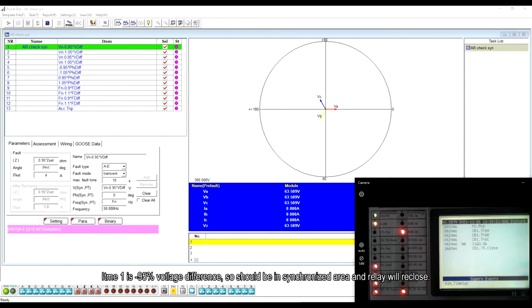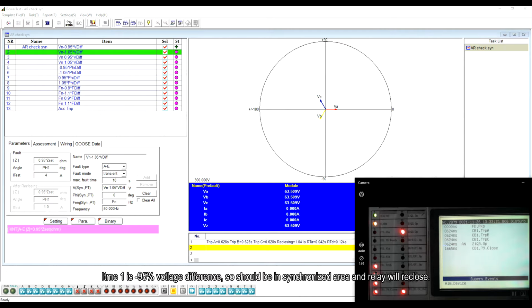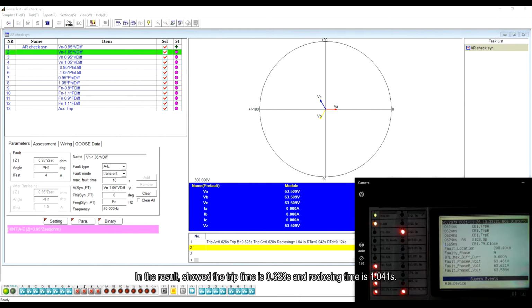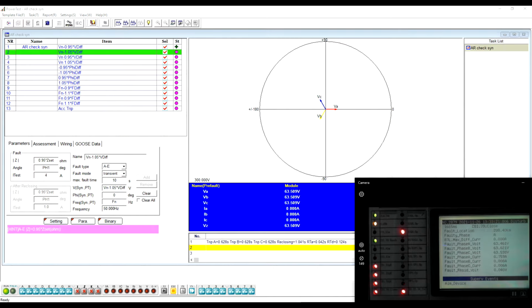Item 1 is negative 95% voltage difference, so should be in synchronized area and the relay will reclose. In the result, showed the trip time is 0.628 second and the reclosing time is 1.041 second.